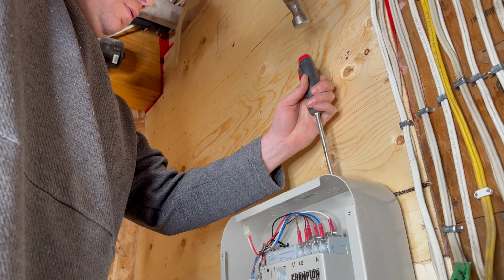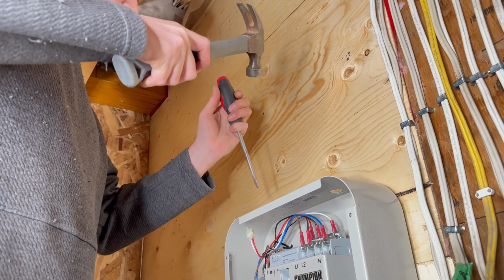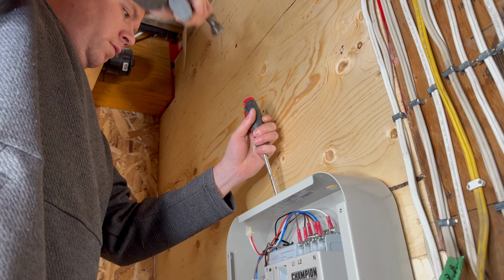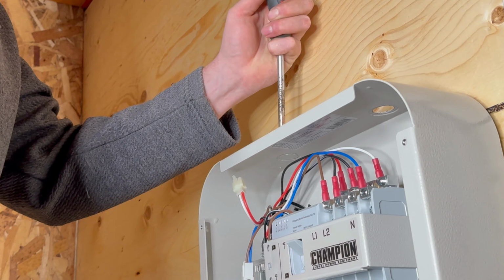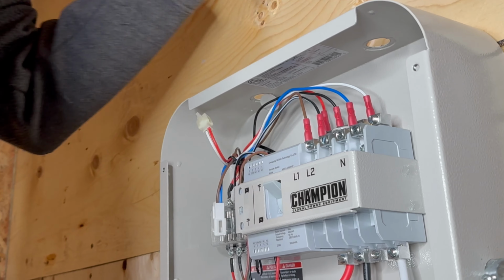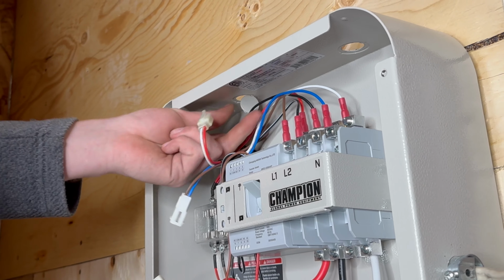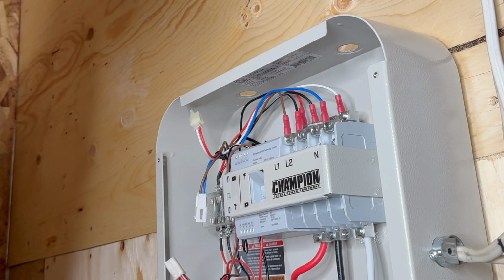Now it's time to start working with some heavier cable. Mark is opening up some knockouts here to allow a cable from the main panel to enter the transfer switch, and this provides electricity to your essential circuits when the grid is up.